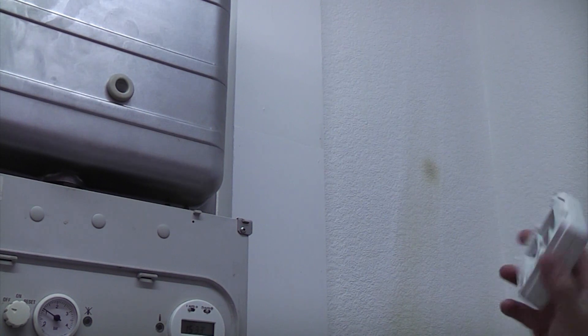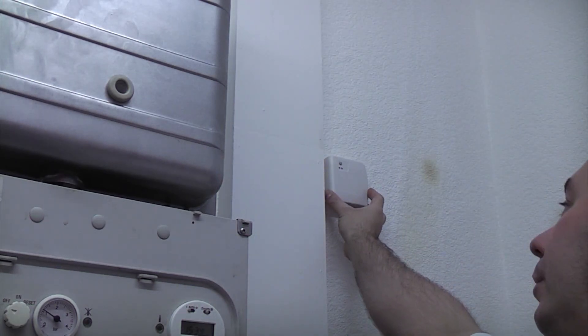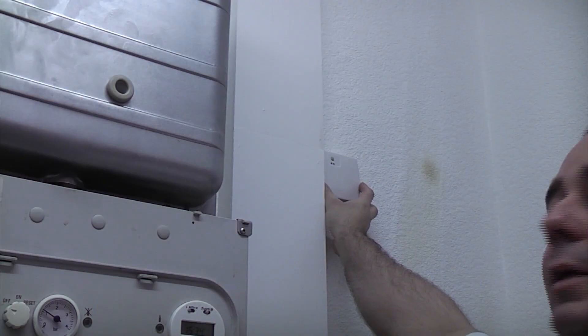Before we connect any wires to the boiler, I am going to start siting the actual receiver box, and I have read the instructions, and it says that it needs to be at least 30cm away from your actual boiler or anything metallic, such as a cooker or anything. So what I am going to do is I am going to stick it approximately there.